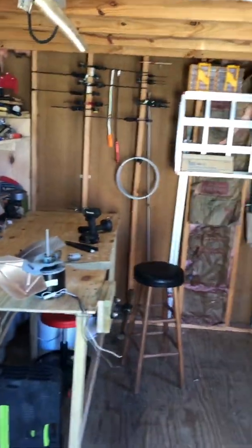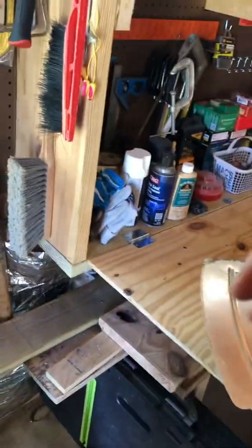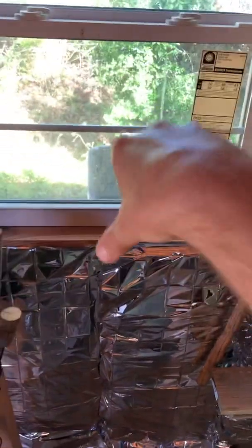Right? That's important. But if the outside air is actually too hot to be comfortable, then you do have to chill it. So when it gets to be 110 or 95 or whatever outside, ventilation isn't going to save you. It's just going to take really hot air and remove it with still too hot air. So you do need to have some kind of chilling method. The way evaporative cooling fundamentally does that is we are putting the heat from the outside air, where it's like 100 and something, into the water and evaporating the water into the air. That phase transformation represents an enormous amount of power.